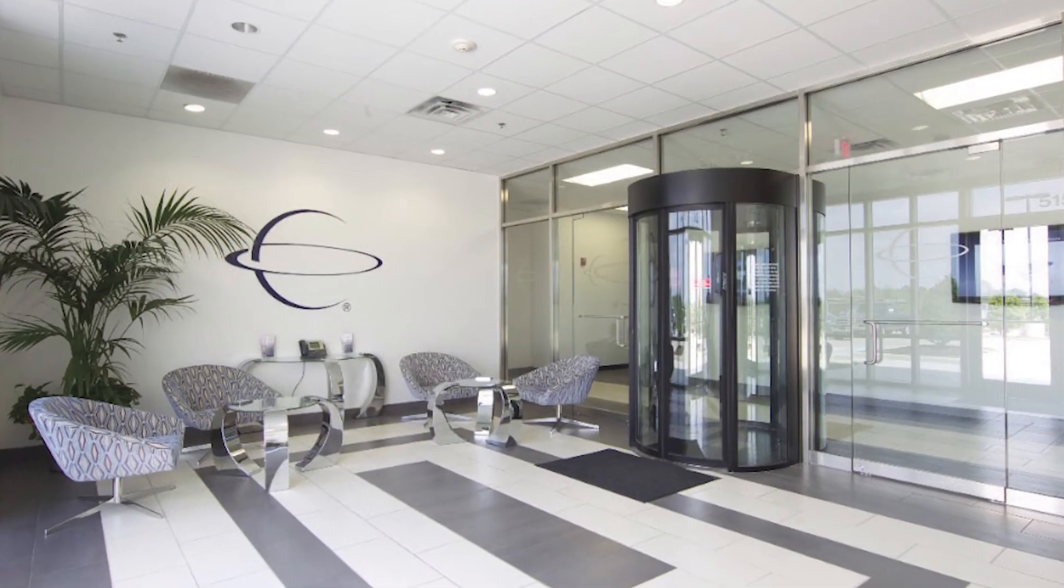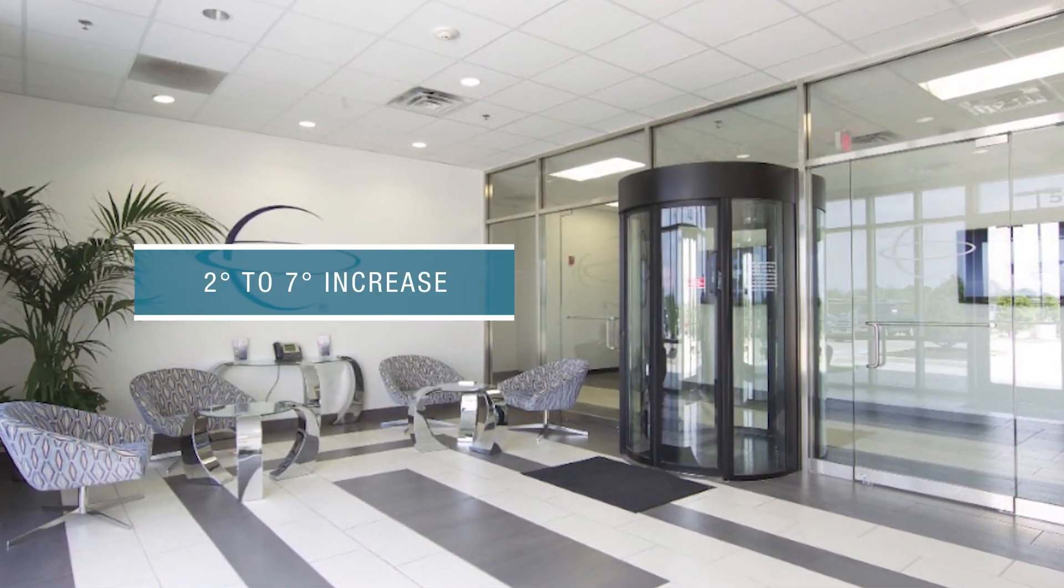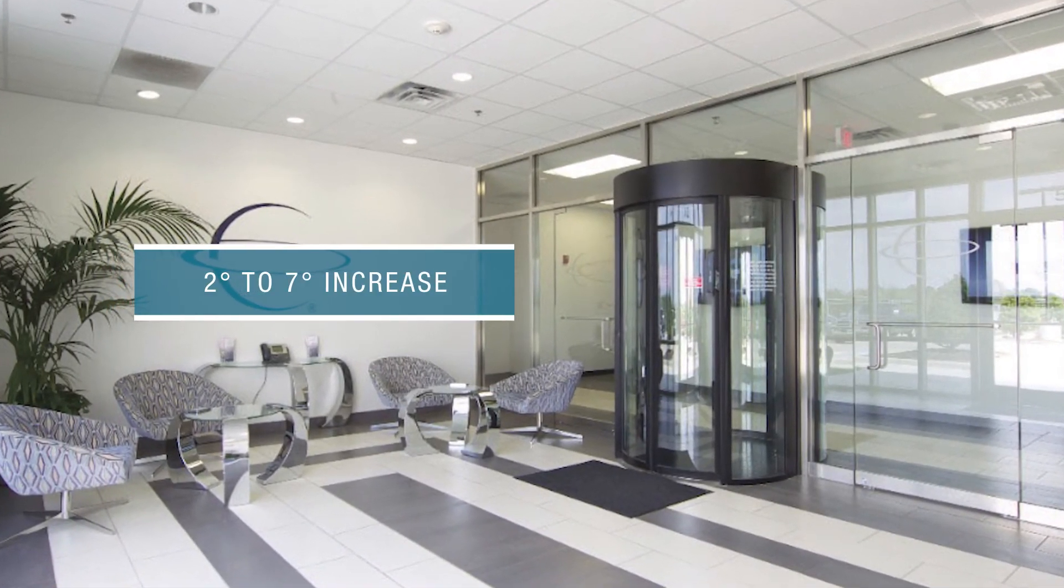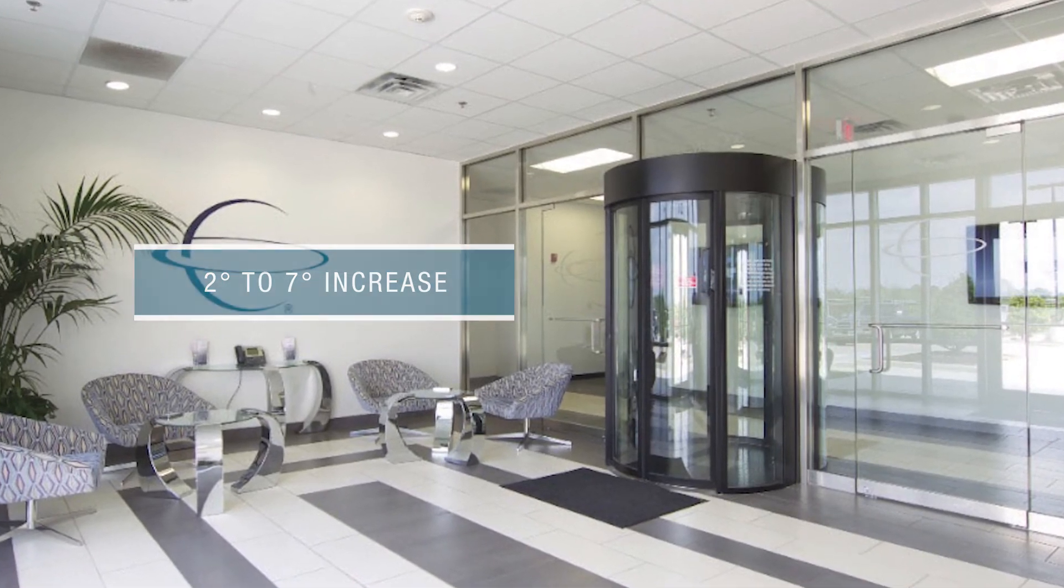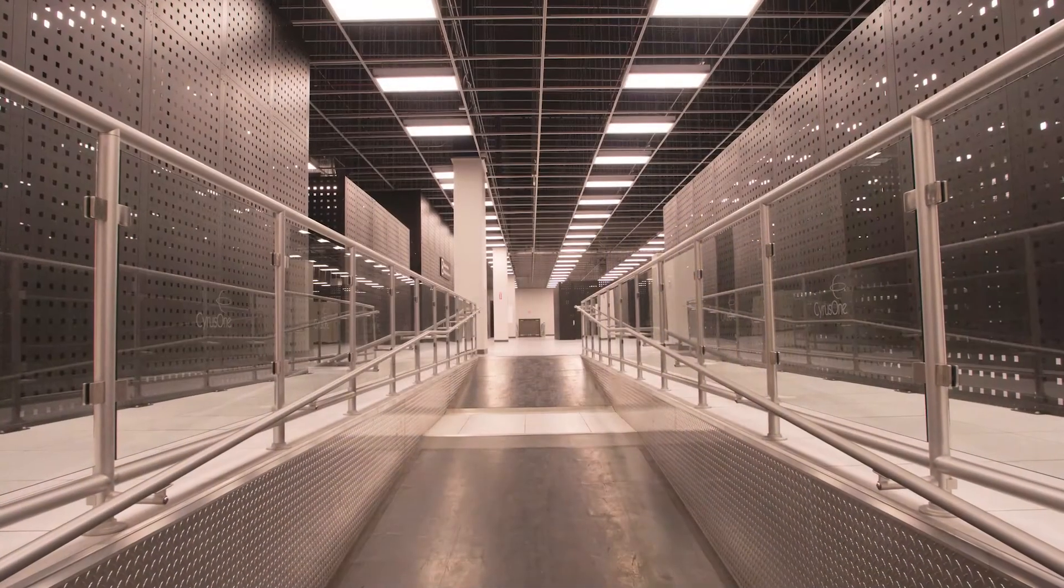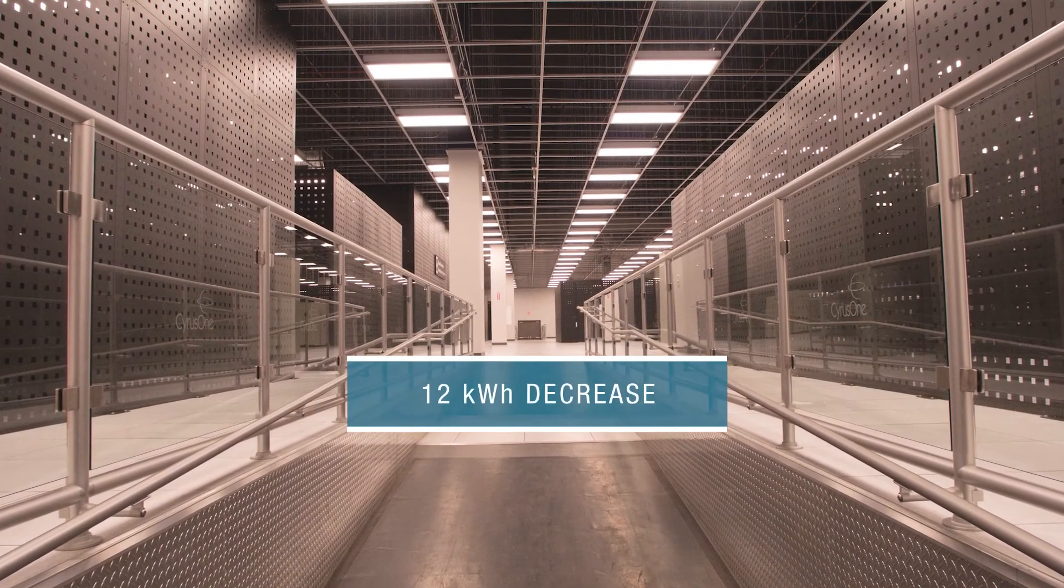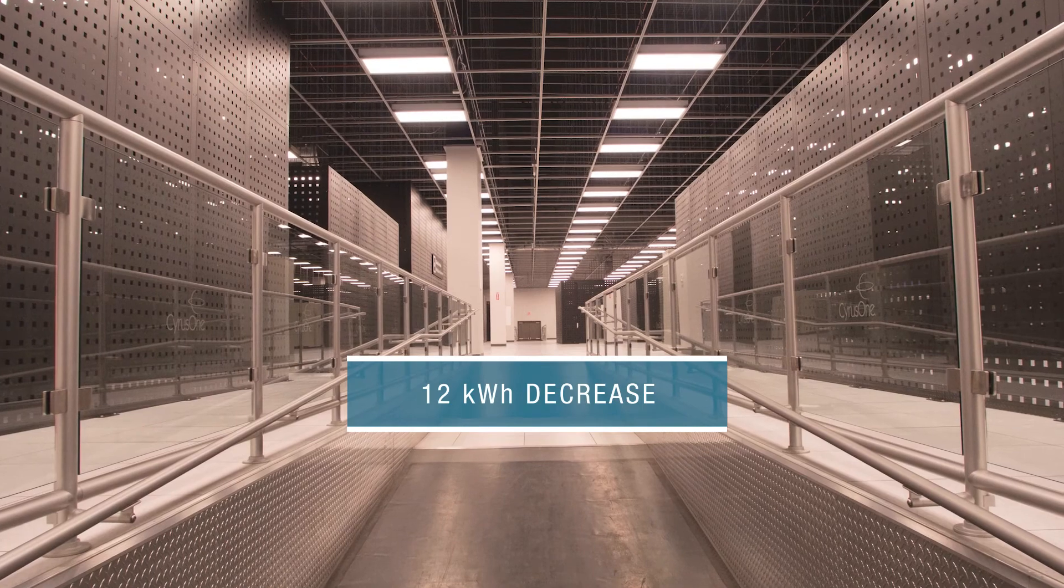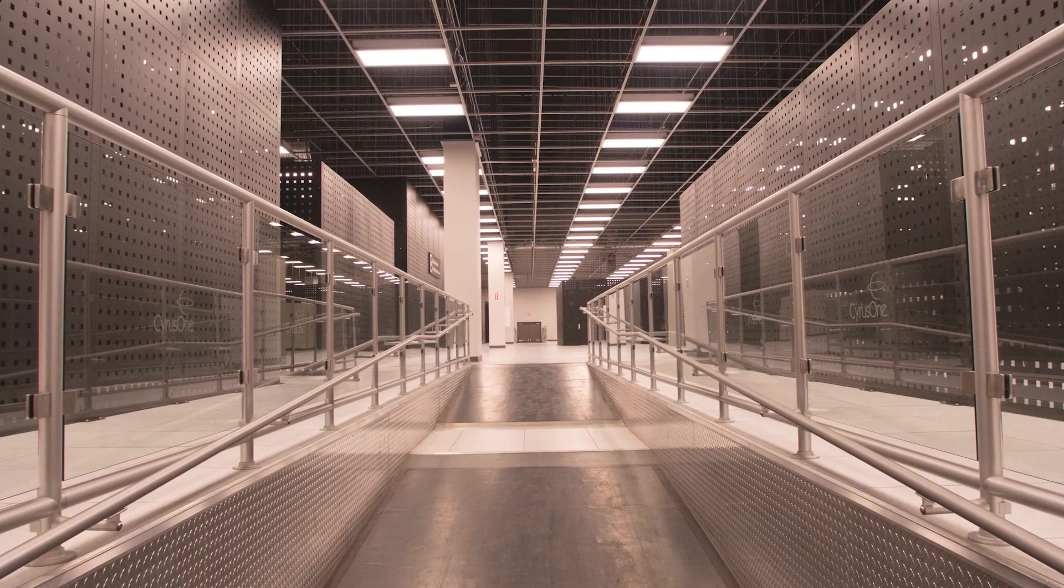Today, Cyrus One is experiencing a 2 to 7 degree increase in return air temperature set points throughout the facility, with the refrigeration power decreased by 12 kilowatts, and the floor pressure is now perfectly balanced.